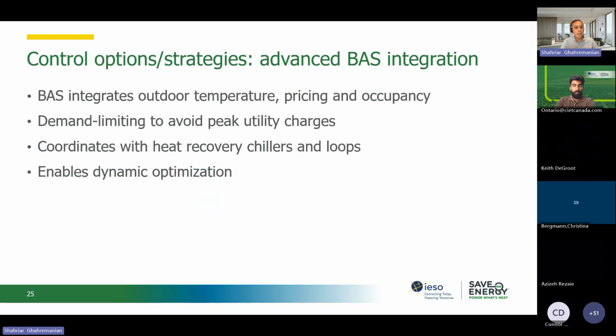So if we have a BAS, and we integrate it with outdoor temperature, the pricing of electricity and other fuel that we use, and also the occupancy profile, then the BAS can decide in a smart way, and we can benefit from that. Or we can have it demand limiting to avoid peak utility charges. During peak hours these days, in very cold hours, we see the peak in our electricity. So maybe it's better we switch to our hybrid system, or coordinate with the heat recovery chiller and the loops that I will speak about later.